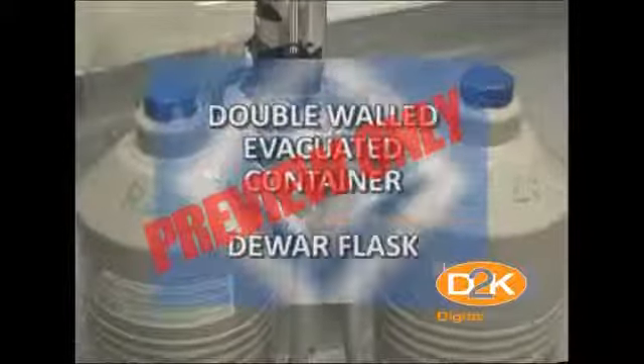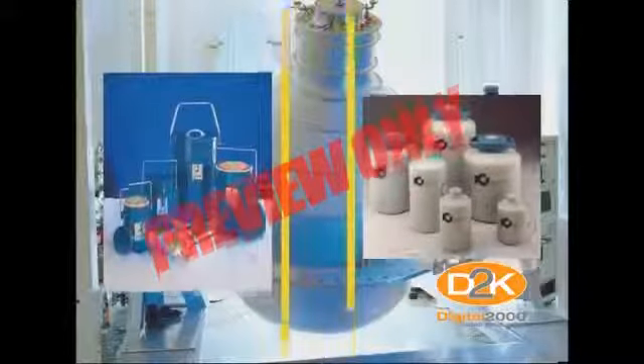Storage of cryogenic fluids is usually in a well-insulated container designed to minimize loss of product due to boil-off. The most common container for cryogenic fluids is a double-walled, evacuated container known as a Dewar flask of either metal or glass. A Dewar flask will contain a metal base which serves as a stand. Exposed glass portions of the container should be taped to minimize the flying glass hazard if the container should break or implode. Metal containers are generally used for larger quantities of cryogenic fluids.